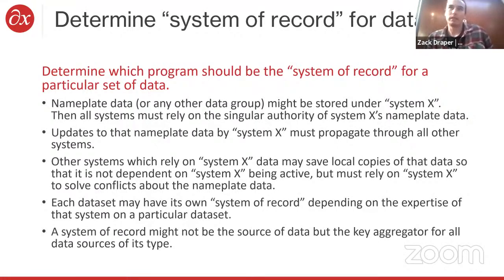So determining a system of record is important for understanding particular data sets and what's good for a particular data set. There may be a software program that's really good at tracking nameplate data. One might be good at DGA data. Another one might be really good at power factor testing. And all of those systems will have to communicate with each other. But it's important to establish one of those systems as being the system of record for a particular data set.